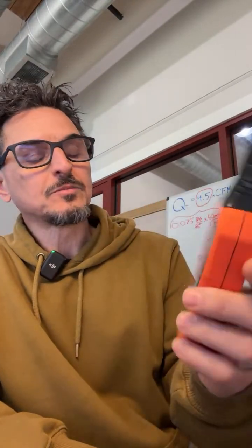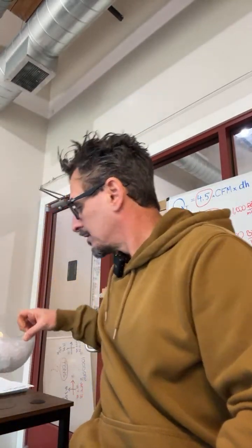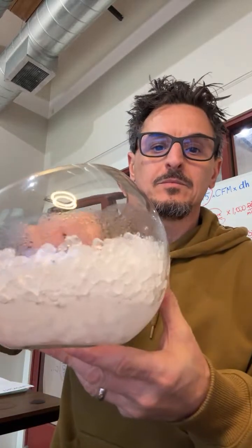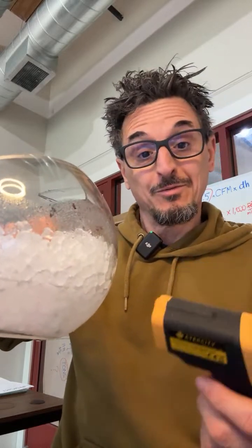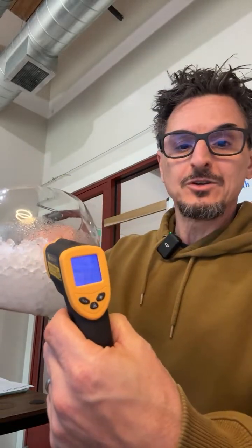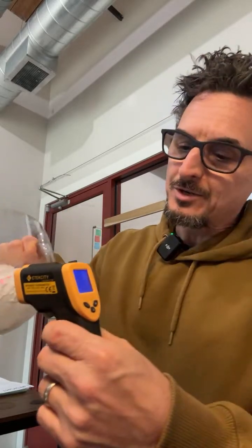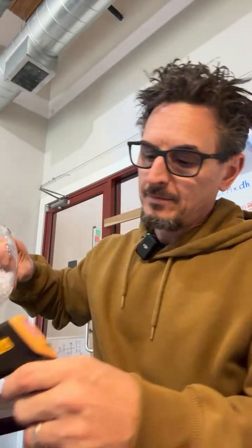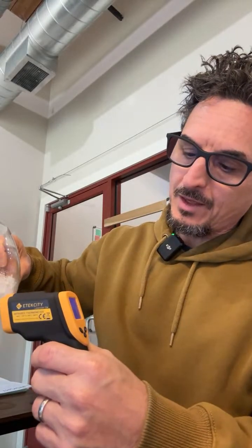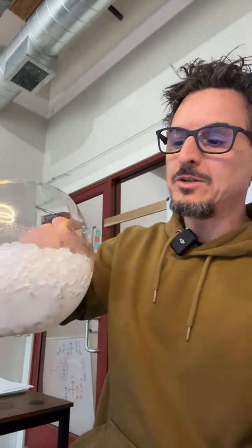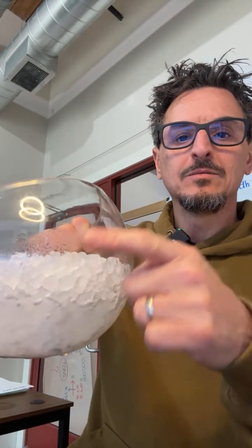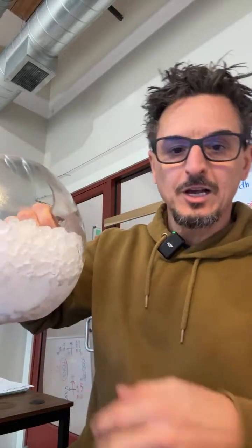So I've got an example to show you that. So the dew point in here is 57-ish, so any surface colder than that will condense water. And I've had this bowl of ice sitting here for a while, and you could imagine, this isn't a big mystery, but this surface temperature is going to be colder than the dew point of the air, right? The surface temperature here is about 37 degrees. So I don't know if you could see that or not, but you can see there's ample condensation here. It's actually dripping all over the desk.